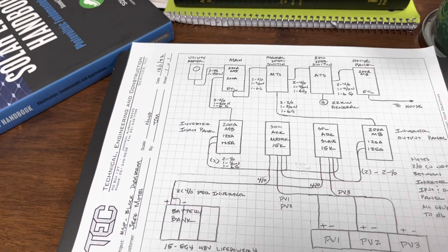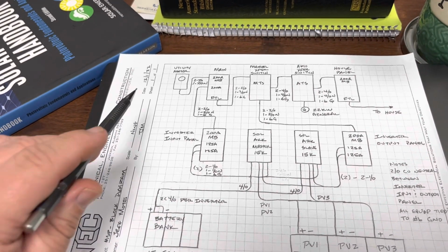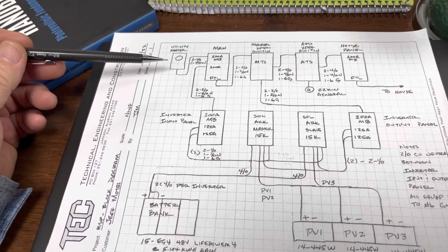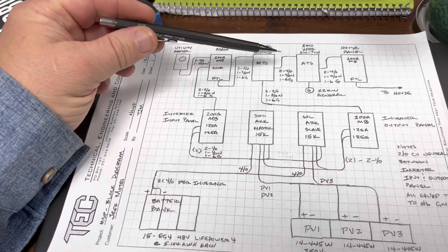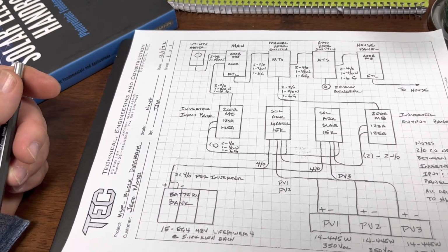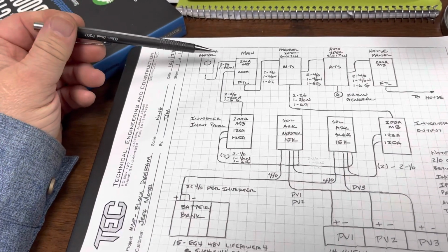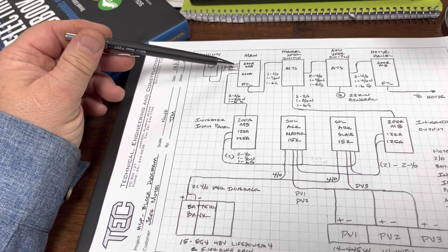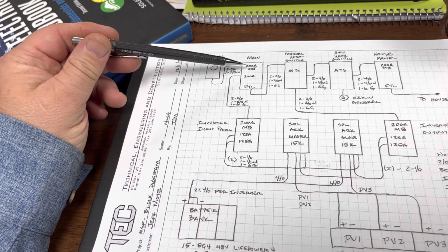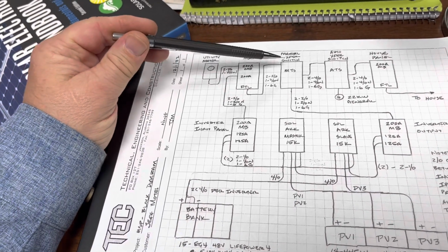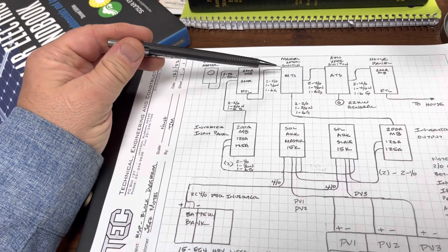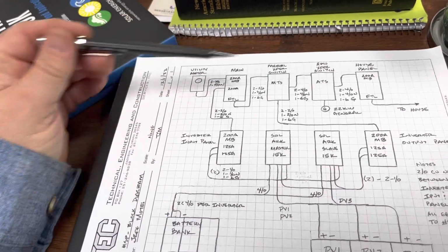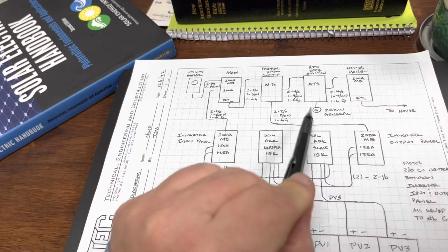Okay, so my intention was to develop my solar power system and put it into my electrical system between my utility meter and my automatic transfer switch. To do that, I had to install a new 200 amp main panel for my meter to go to. And from that 200 amp main panel, I feed to one of the source sides of a manual transfer switch. And the output of that manual transfer switch fed back to my automatic transfer switch. And then this stayed the same.